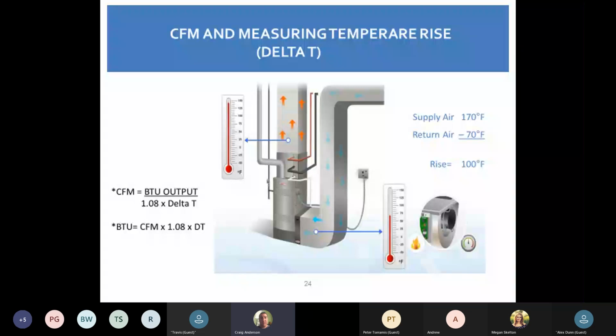Filters out there in the market, there's 5-inch ones, 4-inch ones. They are fantastic. They're pleated. It's giving us a lot of airflow. We're running into problems with 3M filters that are out there. They're like cardboard. I've seen one change our temperature rise 30 degrees. They're crazy. That was new out of the package. So we really need to be mindful of our temperature rises.